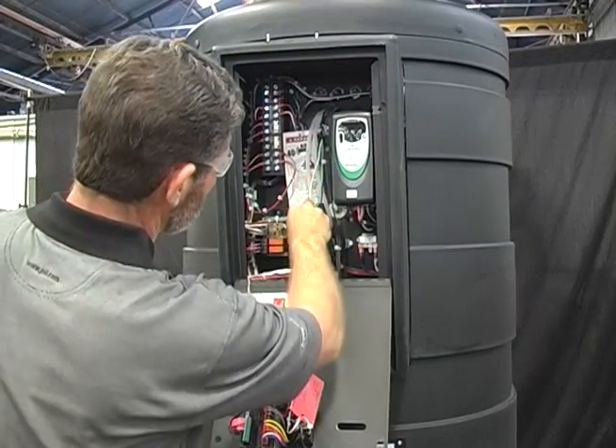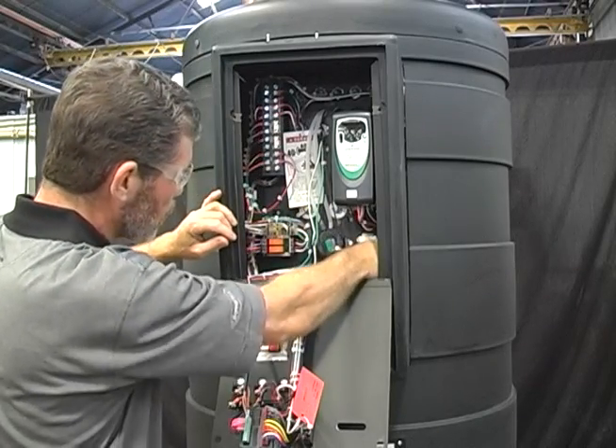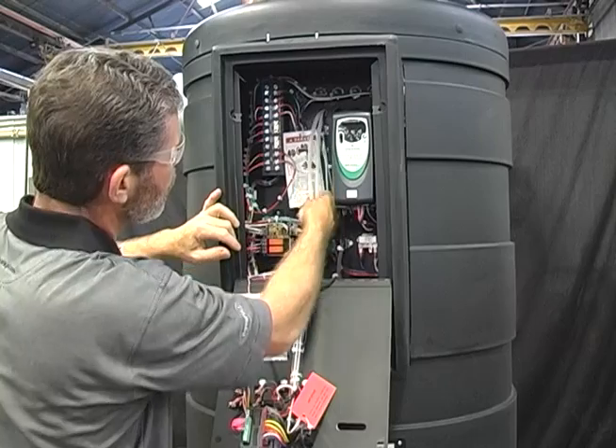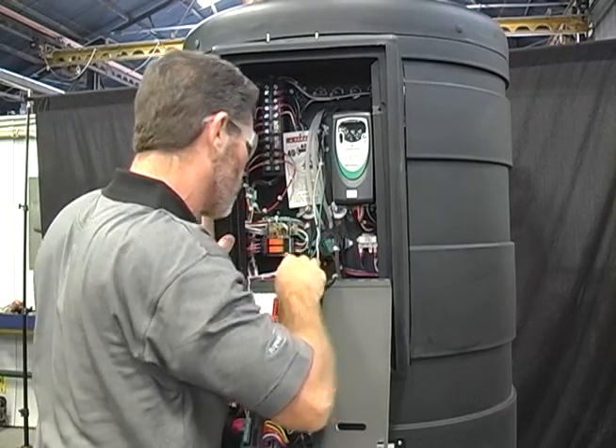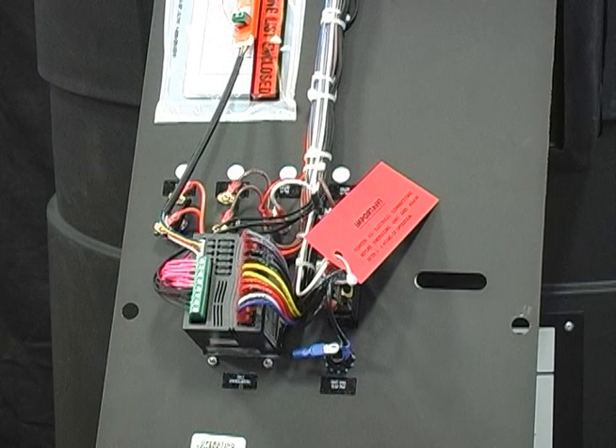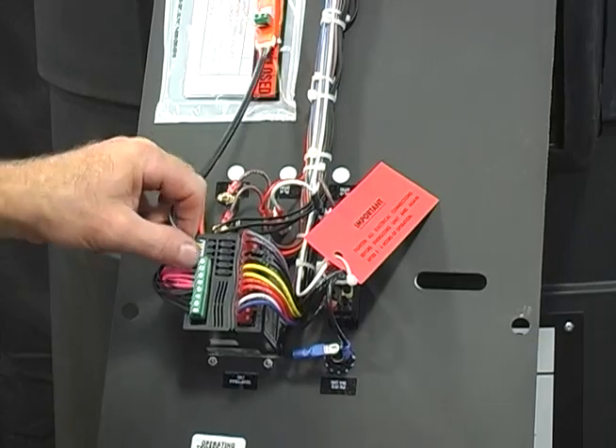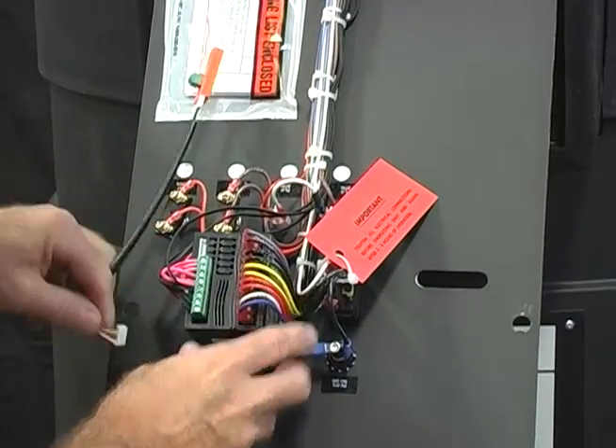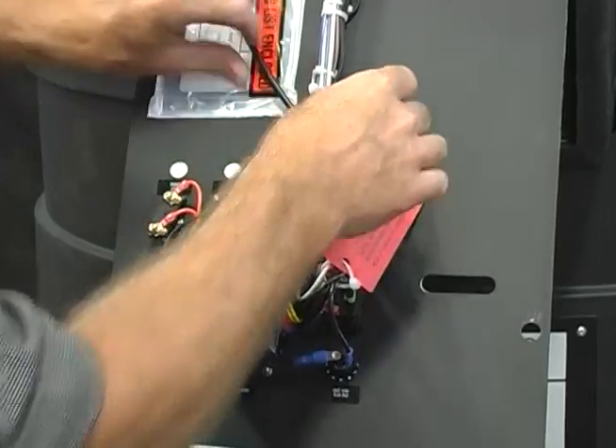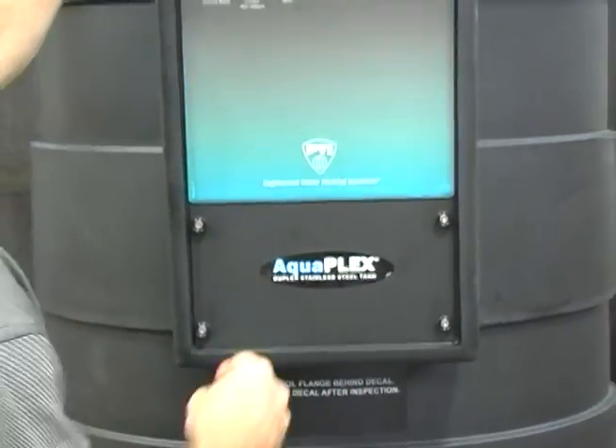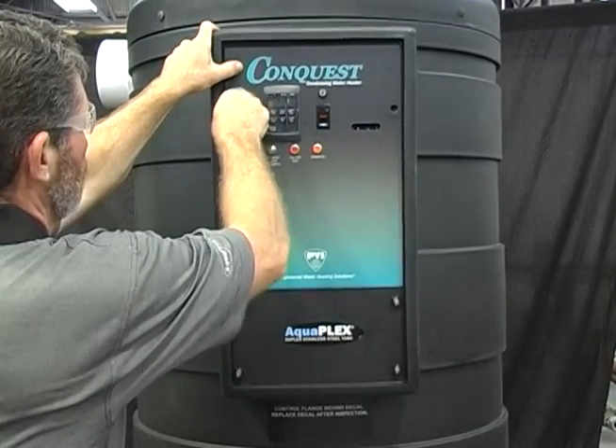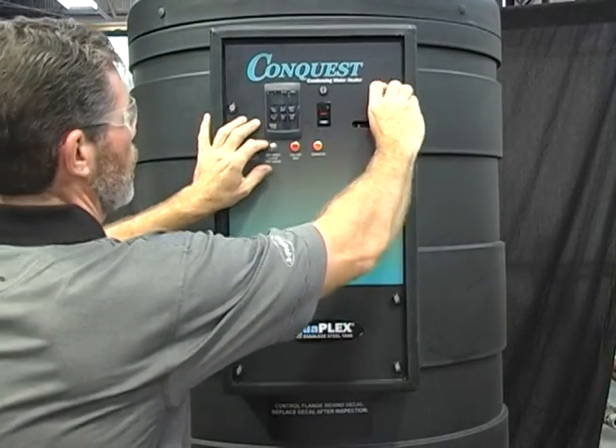With the panel open, once again visually and physically check for loose wires and look for any obvious damage to electrical components. Check to see if a network type BAS connection is made to the water heater. This is done by looking at the back of the TempTrack operating control to see if an RS-485 cable is plugged in. If so, remove the plug until startup of the water heater is complete. This cable will have to be reconnected after startup. Close and secure the electrical box. The circuit breaker should remain in the off position until later in the startup process.